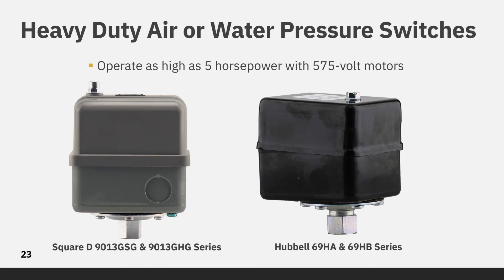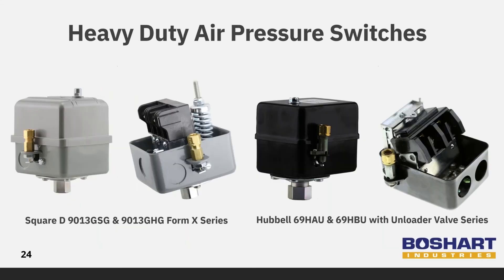Heavy duty air or water pressure switches are used with large pumps and commercial compressors up to 250 psi, 2 horsepower on 120 volt motors and up to 5 horsepower on 240 volt motors. They can operate as high as 5 horsepower with 575 volt motors. Heavy duty air pressure switches can also be equipped with unloader valves as previously mentioned.